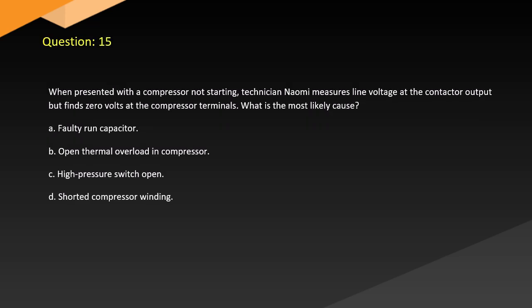Question 15. When presented with a compressor not starting, technician Naomi measures line voltage at the contactor output but finds 0 volts at the compressor terminals. What is the most likely cause? A. Faulty run capacitor. B. Open thermal overload in compressor. C. High pressure switch open. D. Shorted compressor winding.